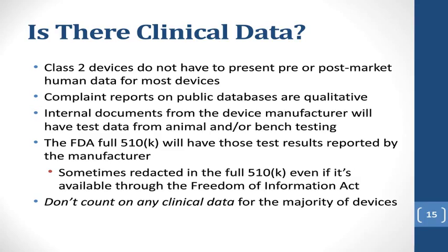What manufacturers do in actual fact is they will have test data. You can use animal testing. There are a lot of really well-known protocols to make sure that there's no sensitivity or that there's biocompatibility and safety, and that's used both with test tubes and also on animals. There are also a lot of protocols where you can test physical properties of devices. You know, how hot or cold can it get? How well does it stand up to this chemical cleaning? Electromagnetic testing, and even mechanical properties like stress testing.